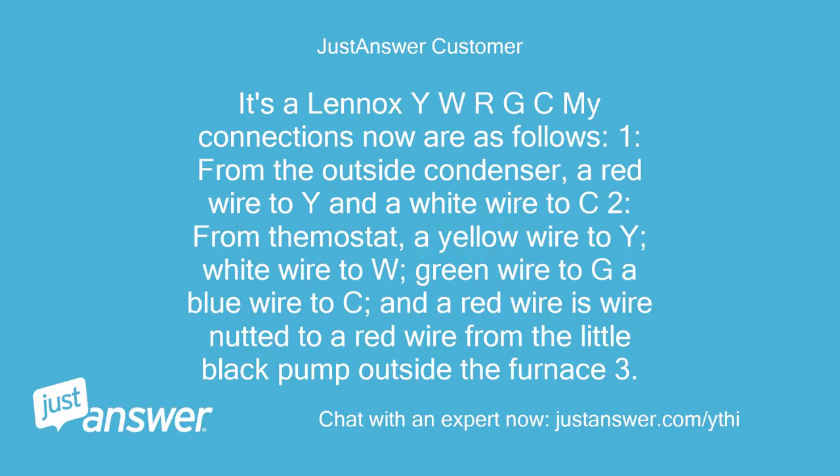It's a Lennox Y, W, R, G, C. See my connections now are as follows. From the outside condenser, a red wire to Y and a white wire to C. From thermostat: a yellow wire to Y, white wire to W, green wire to G, a blue wire to C, and a red wire is wire-nutted to a red wire from the little black pump outside the furnace.